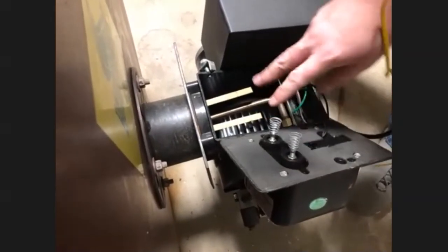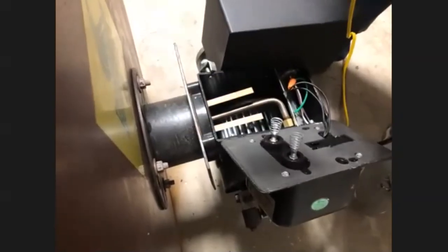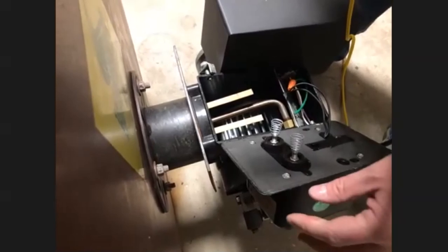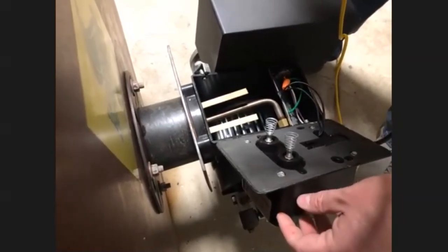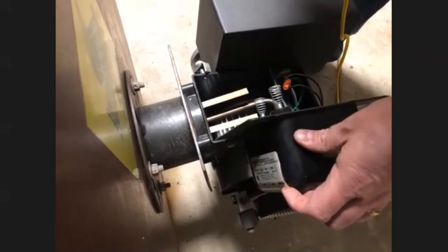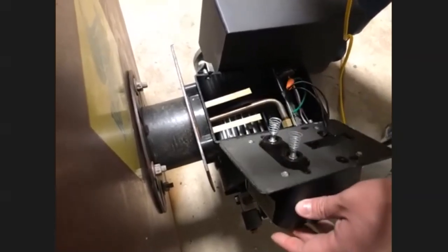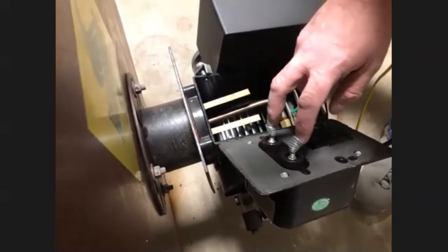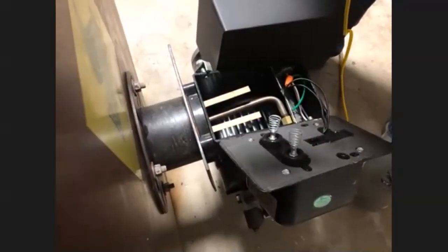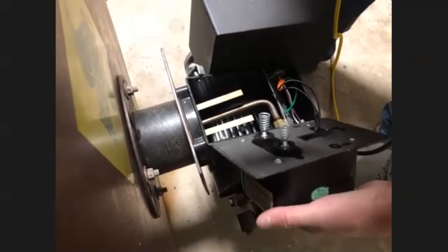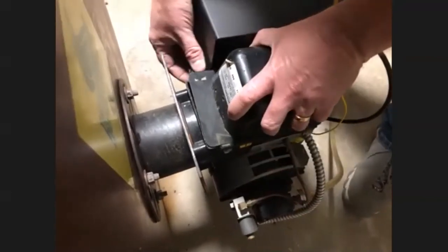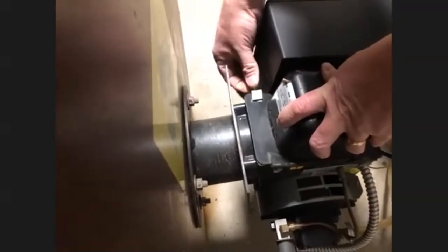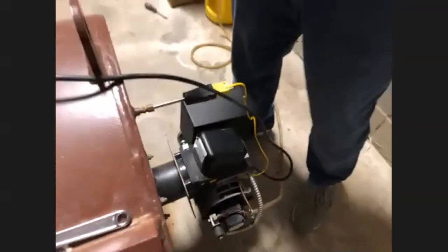And it has two springs coming off and they make contact with bus bars going to your igniters. If you do not have spark, chances are you verify that you have proper voltage coming through, or proper spark any way you want to from this transformer. You must make sure that the springs are making contact on these bus bars. If the transformer is outputting properly, chances are you may have a spark electrode issue, where again, maybe there is a cracked housing on the electrodes, or just maybe a wire where the tips are not adjusted accordingly. Again, the tips will need to be an eighth inch from each other to make sure that the spark is jumping across from each other.